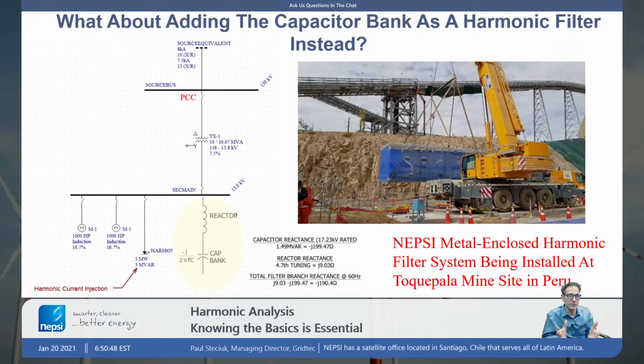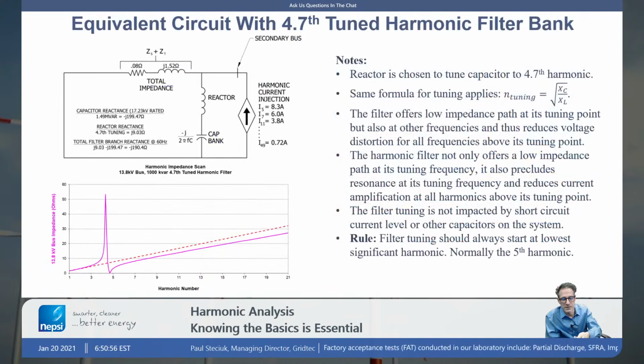The majority of the impedance is capacitive, and therefore it is a reactive power source. So remember, filter banks are installed for 3 reasons. One is reactive compensation. That's the primary reason filters are installed on a network.